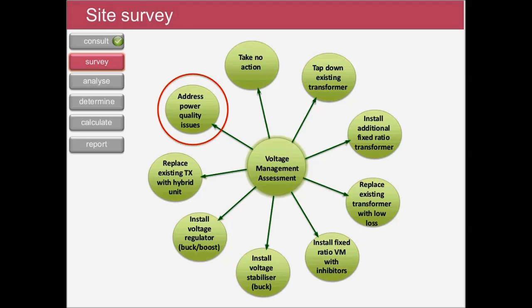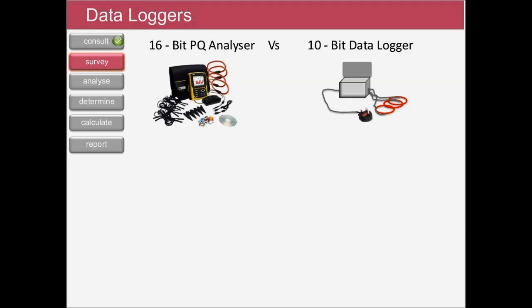It's for this reason why it may be necessary to address existing or foreseeable power quality issues to increase and certainly maintain the stability of the network and the connected loads. However, to be able to successfully identify these issues, a power quality analyzer should be selected over a standard data logger. So let's take a look at some of the advantages of using this kind of data logger. The higher resolution and faster sampling rate provided by a 16-bit power quality analyzer, such as this shown in our new unit here, means that it's more likely to record extreme RMS values.